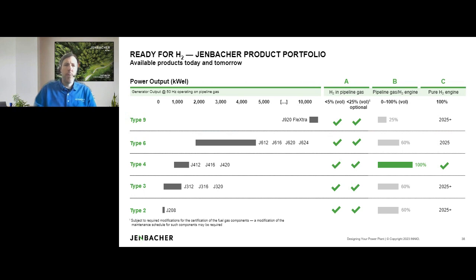If I now show you the slide on hydrogen, it shows again our engines from type 2, 3, 4, 6, and 9. All of these engines are what we call ready for H2, so they can accept as standard low blends around 5%. Then with this optional ready for H2 package, up to 25% hydrogen blended into the natural gas, typically without any derate, so full output.